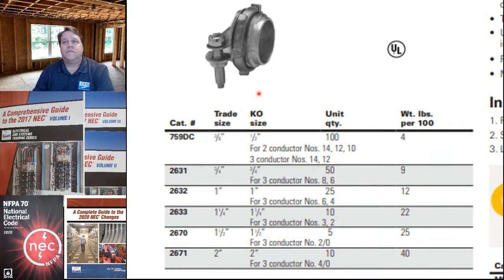So this particular fitting, I don't remember who manufactures it. Trade size 3/8 for a half inch knockout. It says I can put 3 14 or 12 gauge cables. Or I can put two conductors or so. Oh, I misread that. For two conductor 14, 12, and 10 gauge, or three conductor 14 and 12. How many cables can you put through there? I don't know, whatever they might instruct.